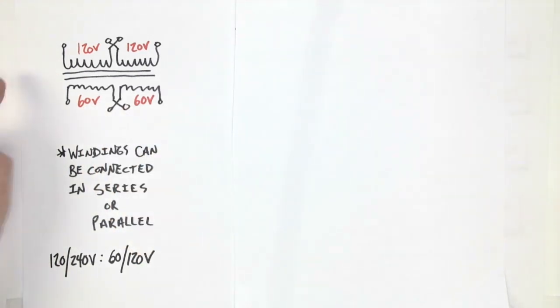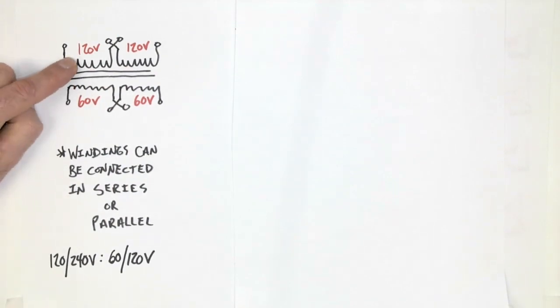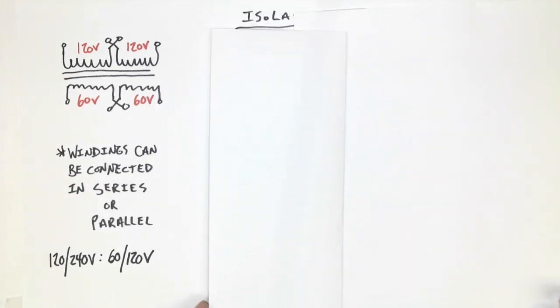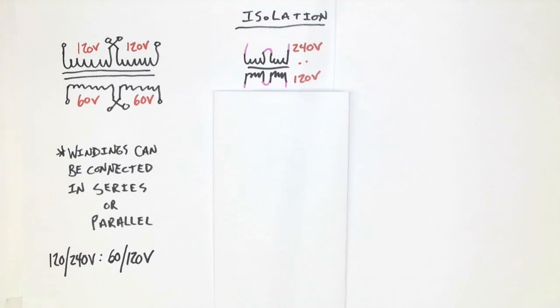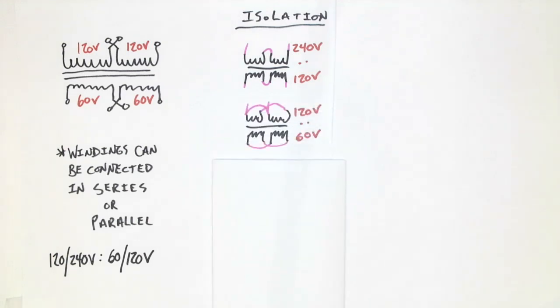Remember, this entire transformer, if it was rated 1000 VA, each one of these individual windings would have a VA rating of 500 VA. Now let's take a look at the different connections that we could have when it comes to an isolation type connection. Well, we could do the primary in series and the secondary in series. That would be 240 source, 120 volt load. We could do them both in parallel, 120 volt source, 60 volt load.